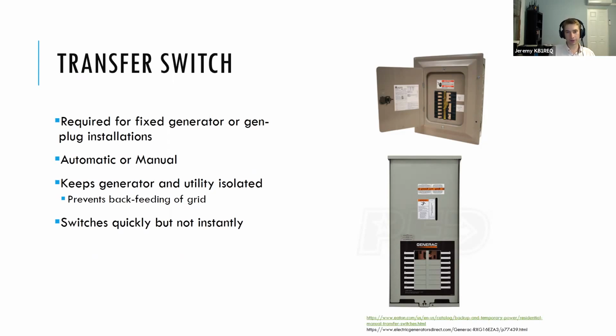And that's where I see UPSs the most: they've got a generator, they've got an ATS, they know that's going to come on in, say, 30 seconds. But within that 30 seconds, all of your AC devices have lost power. They've shut down. You can't rely on this to keep constant power. So that's where a UPS, possibly a backup battery solution, comes into play, because it can bridge the gap and carry the load from power loss to generator start.